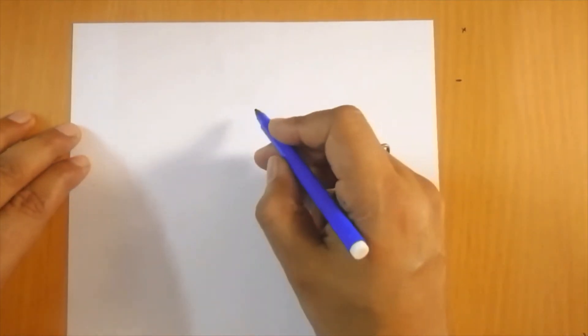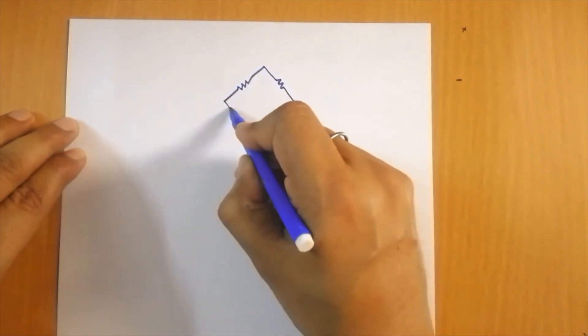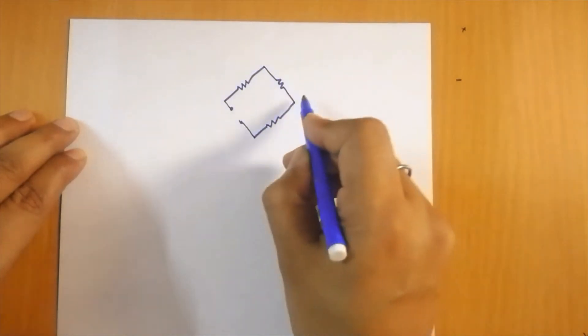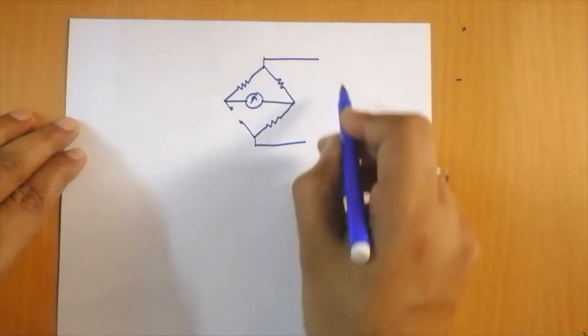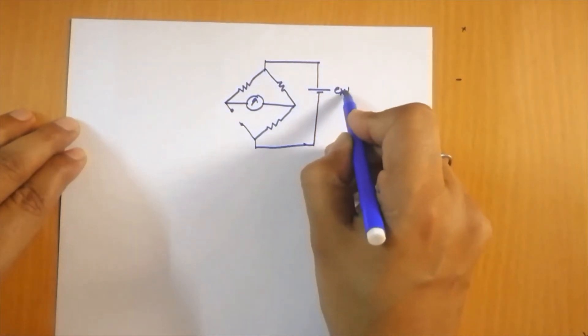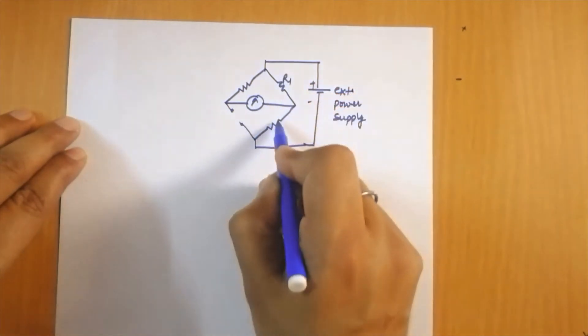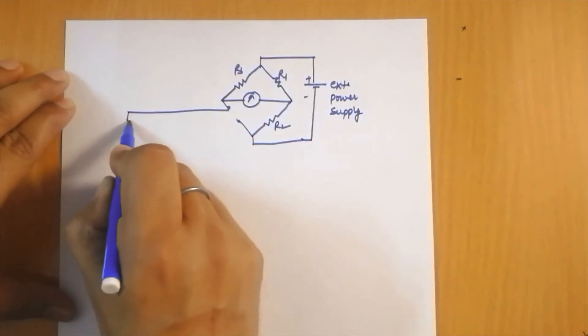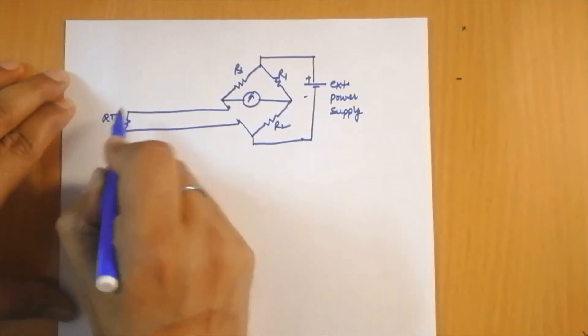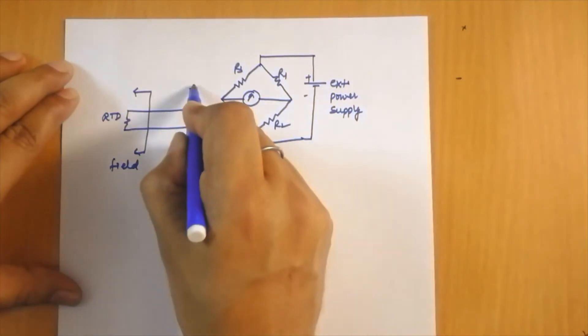To measure unknown temperature using an RTD, we use a Wheatstone bridge circuit. The bridge has four arms with a deflection meter (galvanometer) connected across them and an external power supply, since this is a passive transducer. Three arms contain resistances R1, R2, and R3, and in the fourth arm we connect the RTD. Typically, the RTD is connected in the field while the Wheatstone bridge is in the control room.